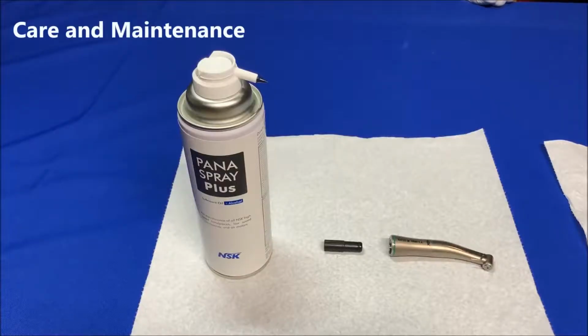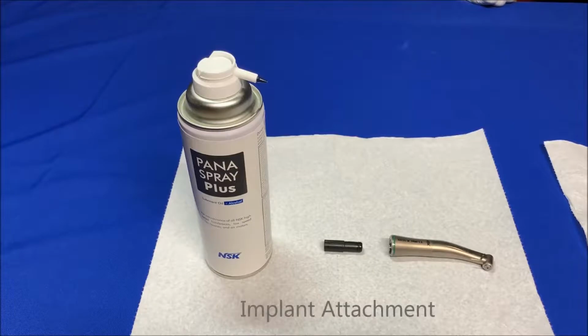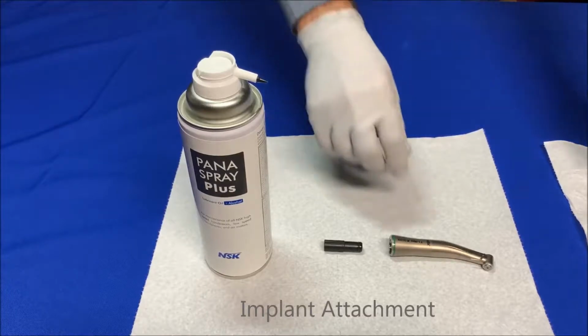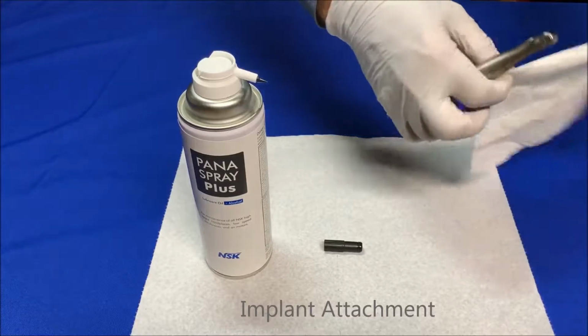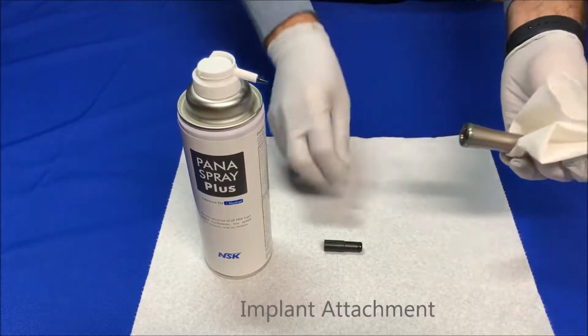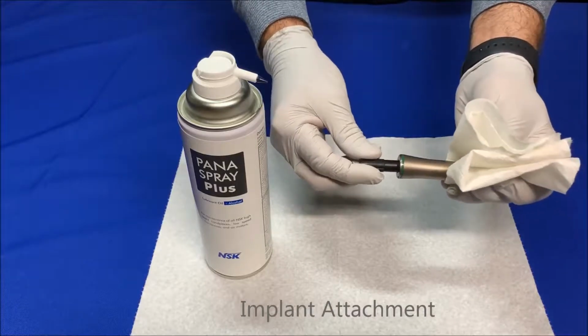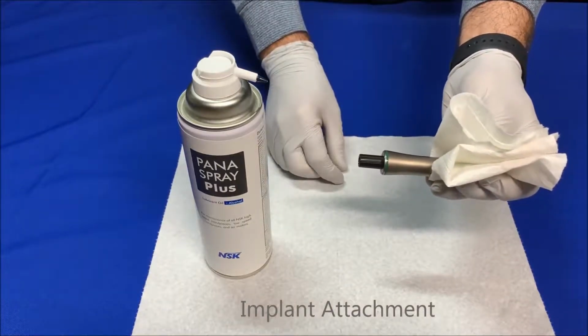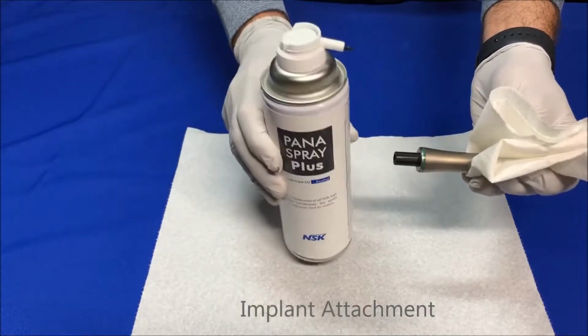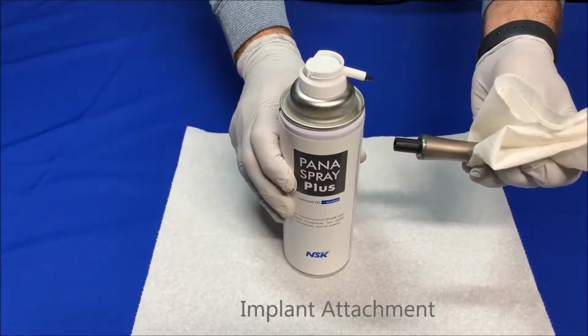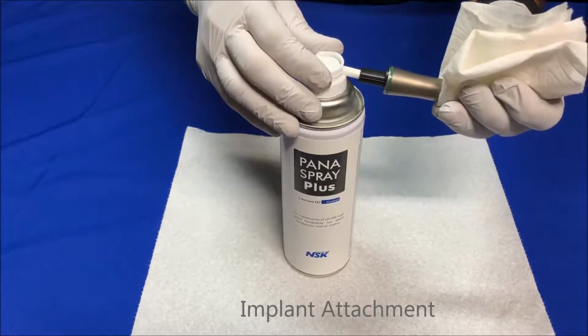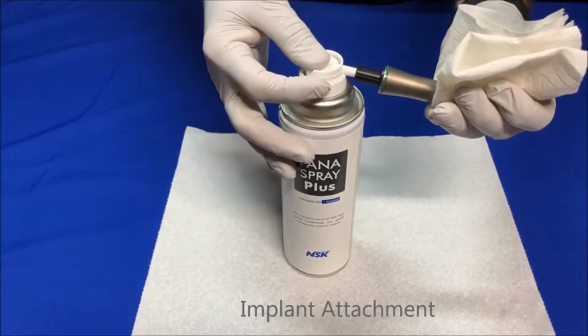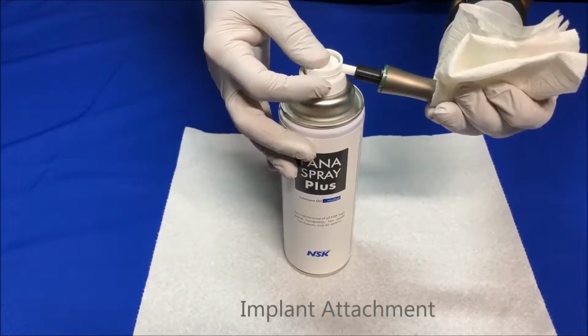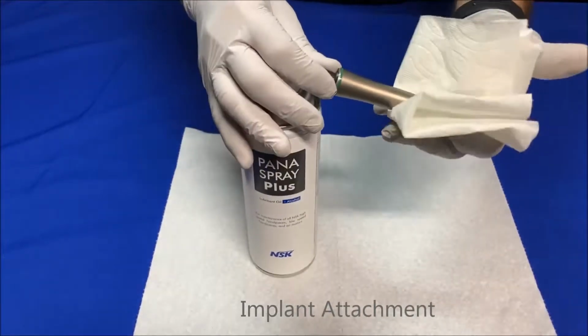Care and maintenance. After each operation, we need to lubricate the handpiece right away. The blood sucked into the internal gears can dry up in less than a minute. Here's how we do it. Cover the head of the attachment with a paper towel. Insert the E-type spray lubricant nozzle into the back of the handpiece. Shake the spray can a few times to mix the lubricant and alcohol. Hold it upright and spray the lubricant for 2 to 3 seconds. If necessary, repeat it a couple of times till clear oil comes out of the head.